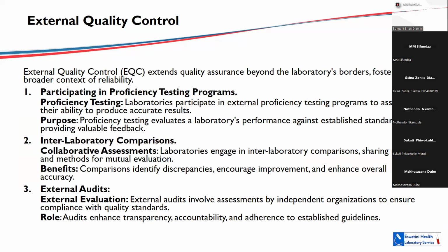External quality control, EQA, is an assurance that is actually beyond the laboratory's borders, fostering a broader context of reliability. That is where we normally register with accredited EQA providers. For example, we have the NHLS that will send out samples to different participating laboratories, and those samples are of known values. So the labs that are participating do not know the value of those samples, then they analyze the samples.